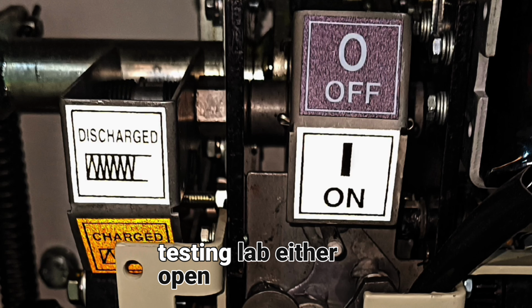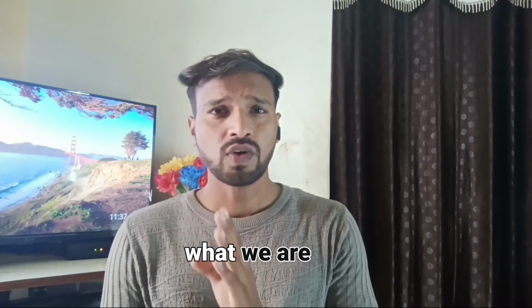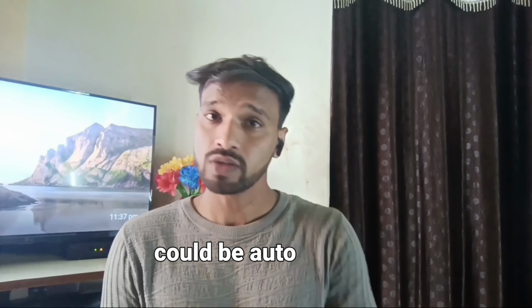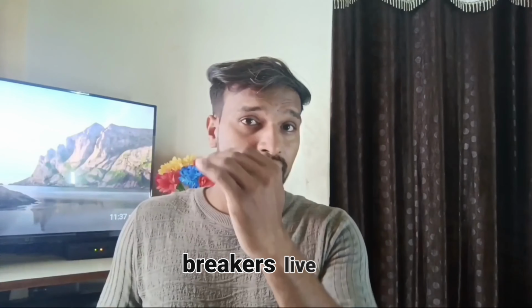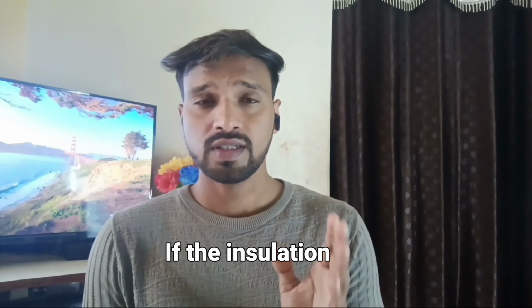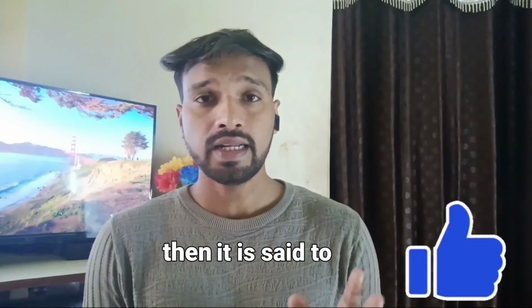So now let's talk about how we actually run the test. First, we place the breaker in the testing lab, either open or closed depending on what we are checking. Then we apply the high voltage using special equipment, which could be an auto transformer, to the breaker's live and grounded parts. It may sound really intense, but it is all done in a controlled environment to ensure safety. During testing, the breaker has to survive high voltage for 1 minute in the power frequency voltage test, and it must handle high impulse shocks in the lightning impulse test. If the insulation holds up and there is no leakage current, then it is said to pass.